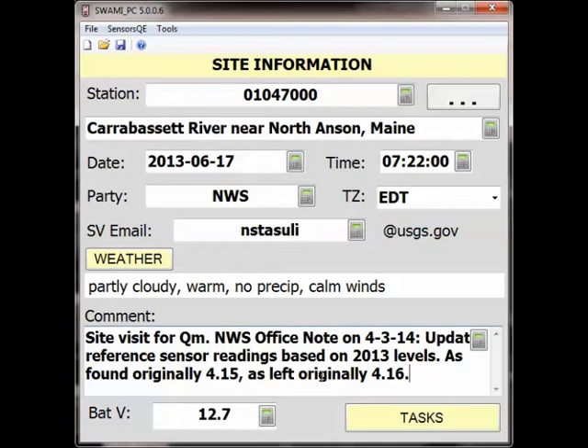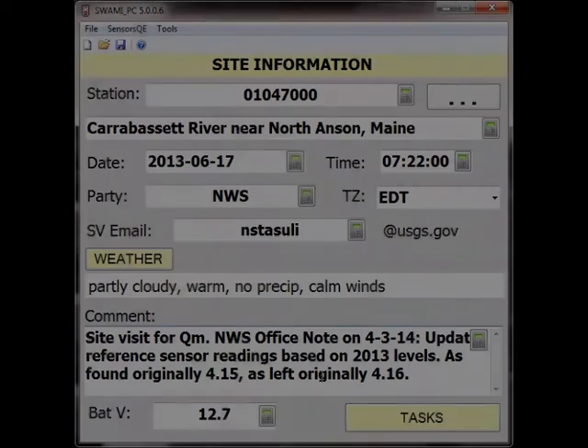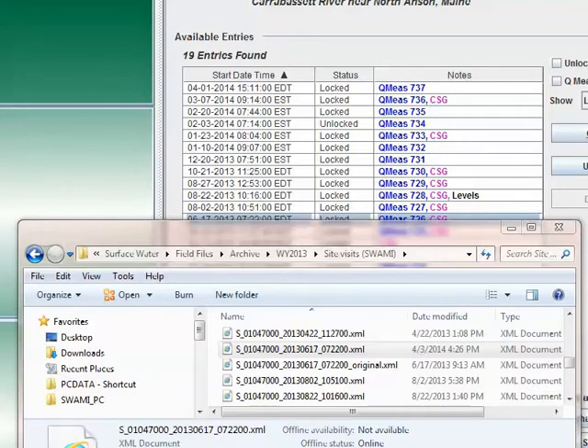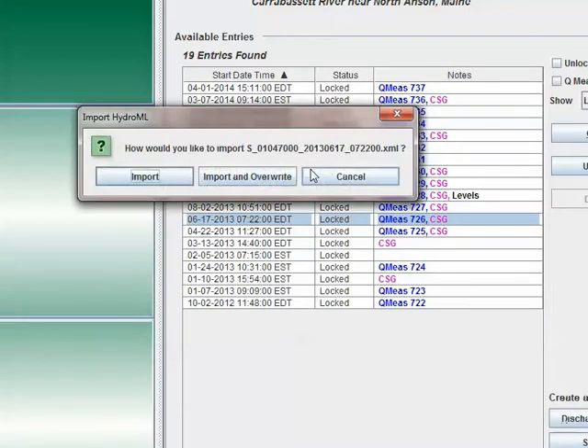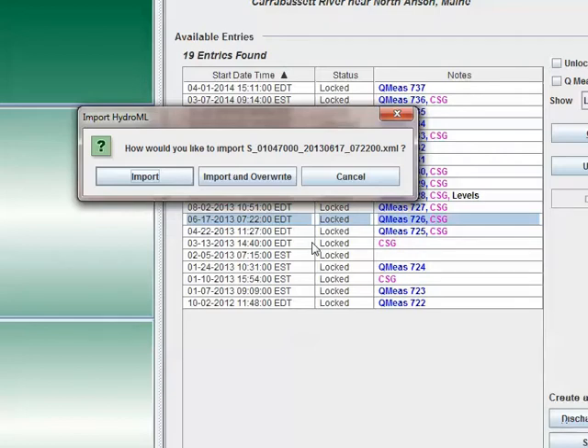This comment could be duplicated in the sensor inspection, but at a minimum it must be made in the main site visit comments. After saving the updated SWAMI file, we can go to the directory where it was saved and drag and drop the file into SiteVisit. We will import and overwrite in this case since the data in SiteVisit matches the SWAMI file perfectly, with the exception of my edits, so there is no risk of losing any data. You would want to check the main SiteVisit comments before importing and overwriting to ensure there was no information added to SiteVisit that could be lost. If using the drag and drop method, saving should only be performed if there have been no violations, which show up with a red X in SiteVisit. Sometimes the only way to fix a violation is by manually editing the field in SiteVisit.